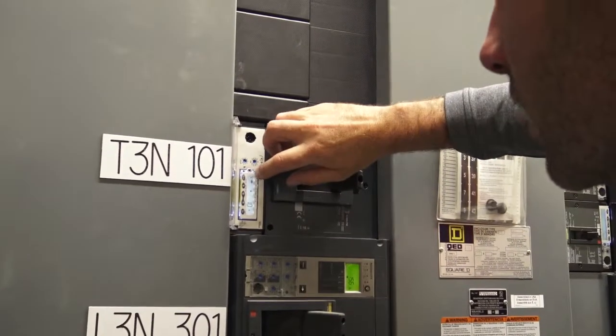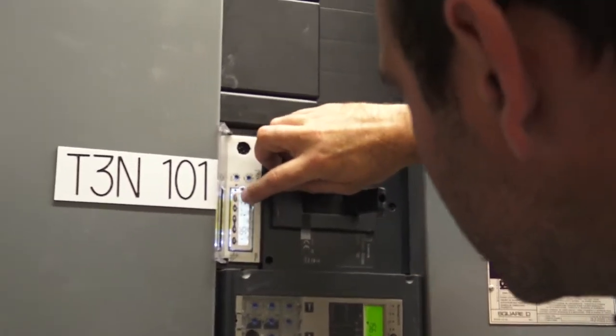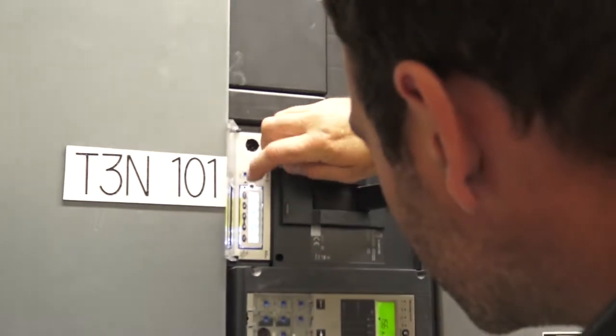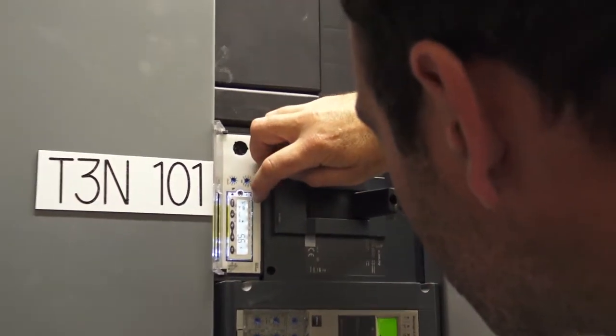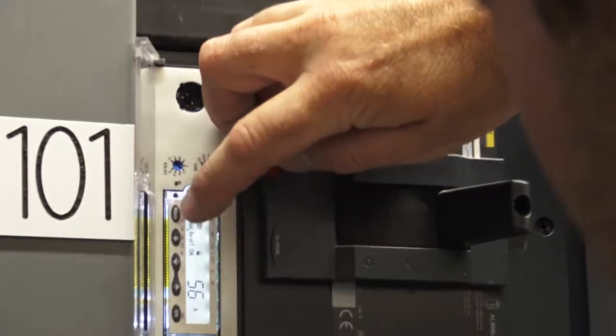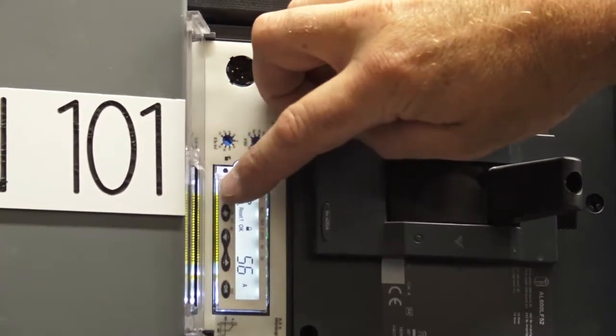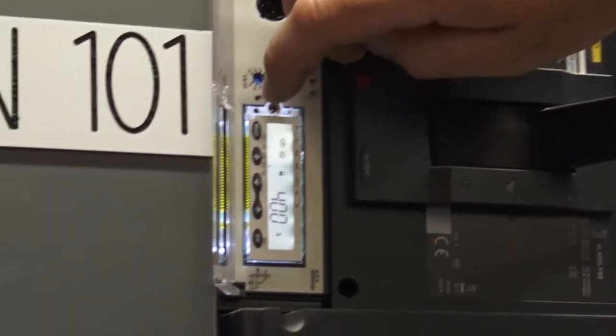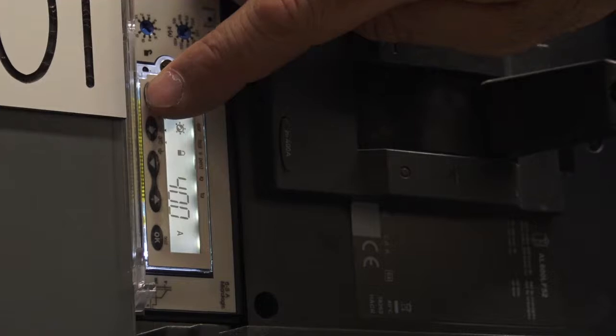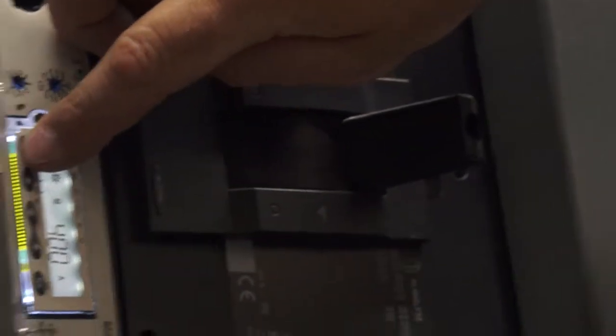So I don't know if you have to get in here, but you can kind of go through. Right now, this is drawing 10 amps. The max load has been 56 amps feeding that transformer. So right now the breaker is set to 400 amps. You could adjust that to lower it if you wanted, but you shouldn't have to.